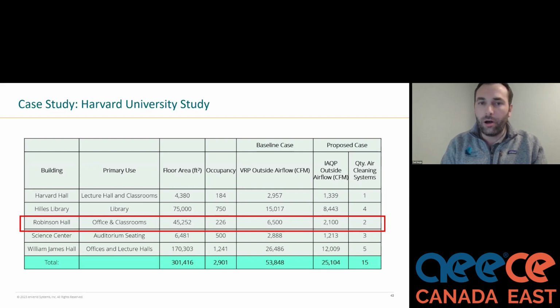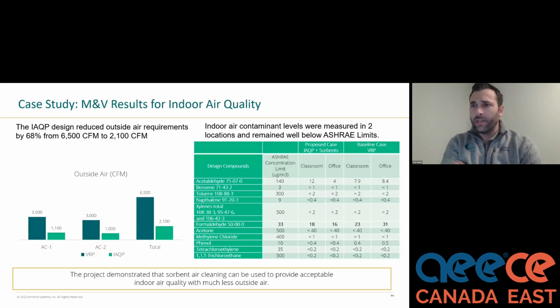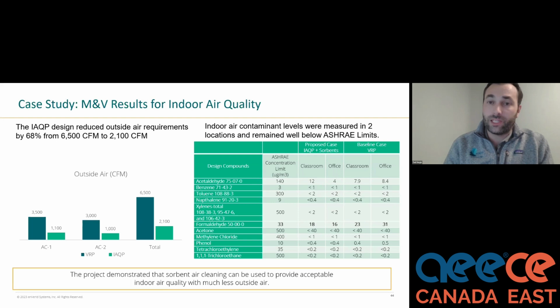And we're going to hone in on Robinson Hall here, where the floor area is 45,000 square feet, 226 occupants, and the outside airflow was cut from 6,500 CFM down to 2,100 CFM, just using 2 filter boxes. The indoor air quality was monitored there, so we got to see the actual impact on a retrofit application of reducing outside air, but adding filtration, which led to a significant reduction of that outside air, 68%, and also significant reduction in terms of the contaminants of concern.